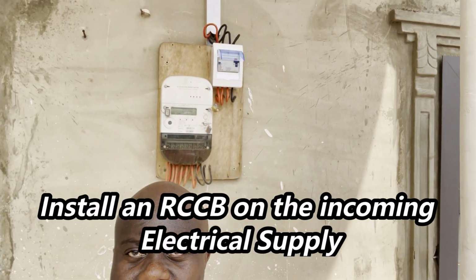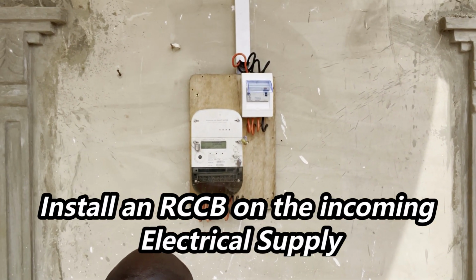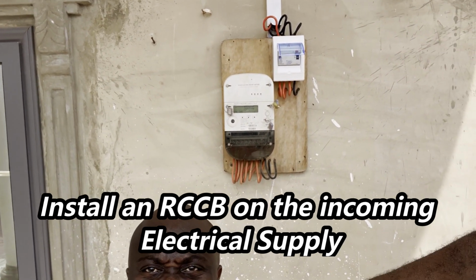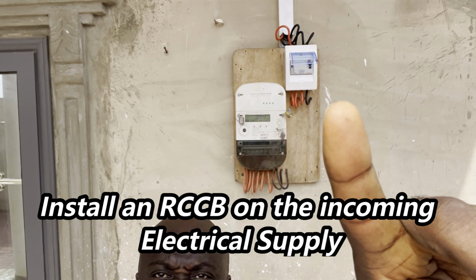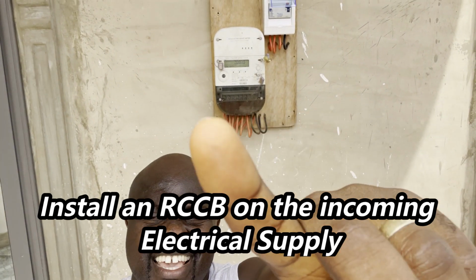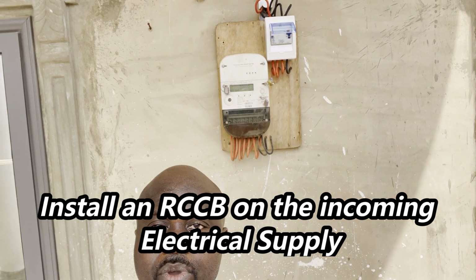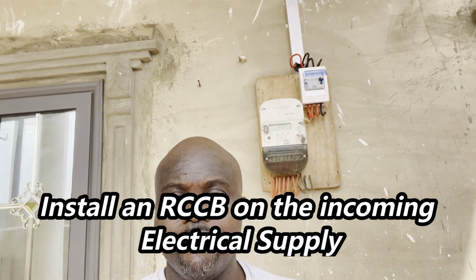The Ghana electrical system's earthing system, without getting too technical, is what we call a TT system. That TT system requires, according to regulations - same as in the UK - the installation of what we call an RCCB on the incomer of the supply. You can see it right above my head: the RCCB is the smaller device just to the side of the meter, which is my ECG prepaid meter. The smaller device beside it is the RCCB, which in full means residual current circuit breaker.